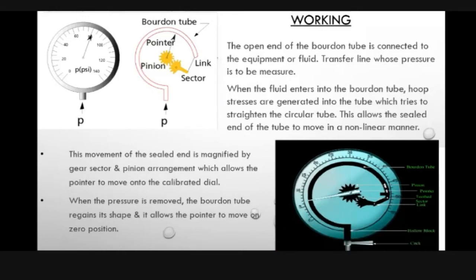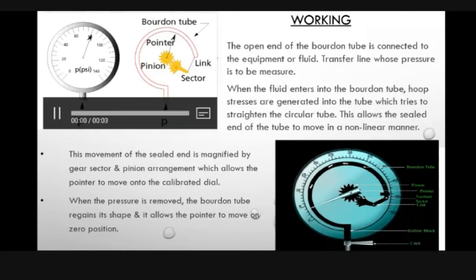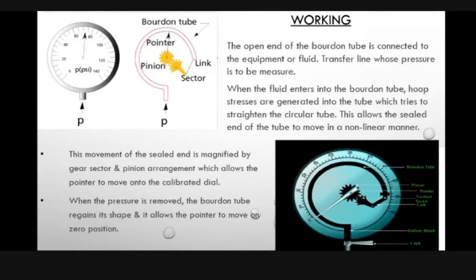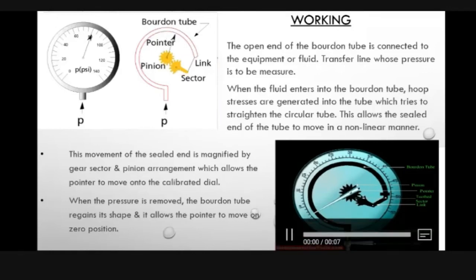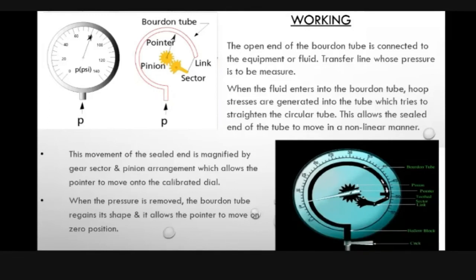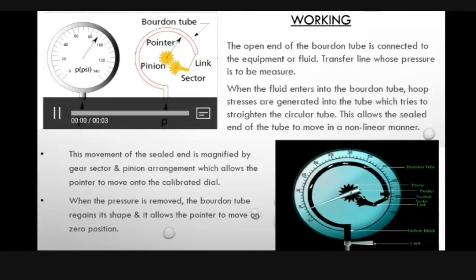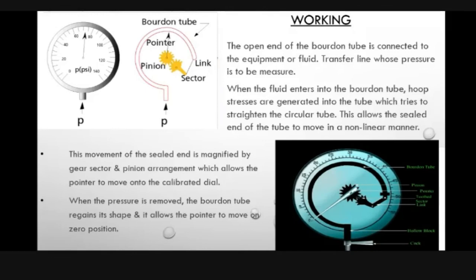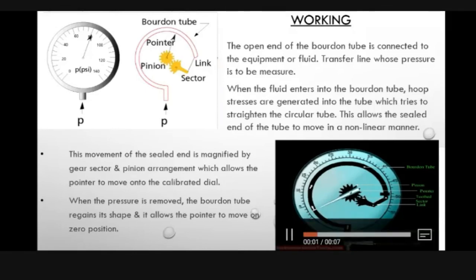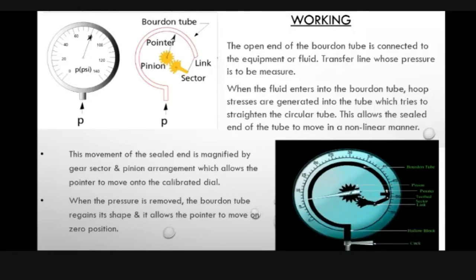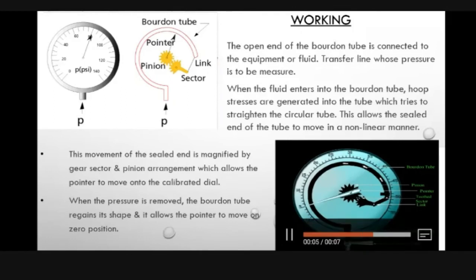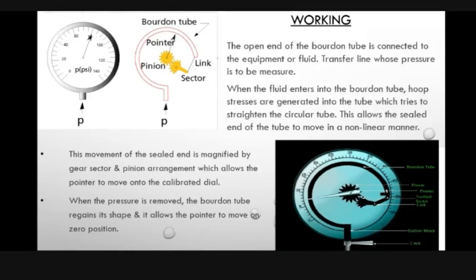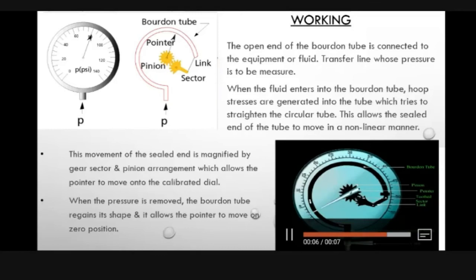Then when the fluid enters the Bourdon tube, the hoop gets stressed. The stress is generated on the hoop and onto the tube, which tries to make the tube circular. This allows the sealed end of the tube to move in a non-linear manner. This movement of the sealed end is then magnified by the gear sector and pinion arrangement, which allows the pointer to move onto the calibrated dial. When the pressure is removed, the Bourdon tube regains its shape and allows the pointer to move to the zero position. Further, over to you, Priyesh.